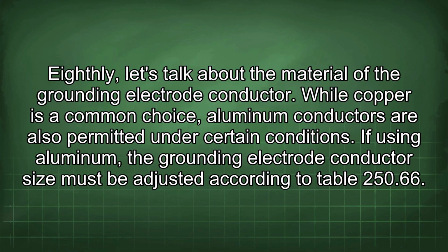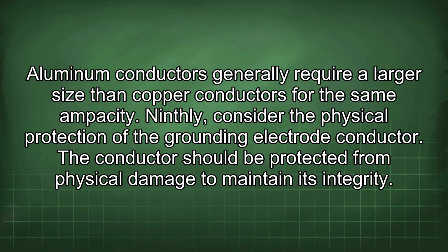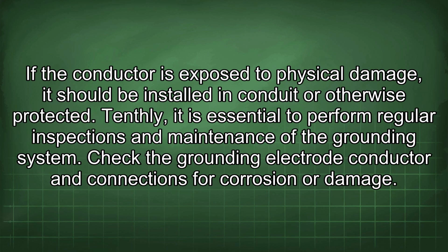Eighthly, let's talk about the material of the grounding electrode conductor. While copper is a common choice, aluminum conductors are also permitted under certain conditions. If using aluminum, the grounding electrode conductor size must be adjusted according to Table 250.66. Aluminum conductors generally require a larger size than copper conductors for the same ampacity. Ninthly, consider the physical protection of the grounding electrode conductor. The conductor should be protected from physical damage to maintain its integrity. If the conductor is exposed to physical damage, it should be installed in conduit or otherwise protected.